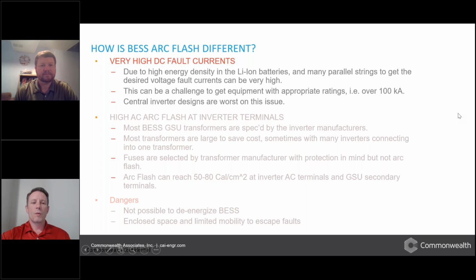As I said before, we were hoping to focus specifically on battery arc flash for BESS systems. So what makes that different than regular arc flash? Number one, lithium batteries are kind of the standard anymore, and they have just a very high energy density in them in general. And then we usually hook up a lot of parallel strings to get the desired voltage. So that makes the fault current just incredibly high.